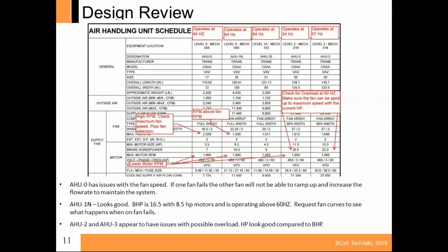I look at air handler 1N, the one right next to it, and I said, okay, that one's running at 64 hertz, which is above 60 hertz, which is fine. I looked at the ratios of the horsepowers. So you have 16.5 is the brake. Each motor is 8.5. And that one looks like it's a pretty acceptable installation. And I think that looks good. And we should probably look at the fan curves and figure out what's going to happen when a motor fails.